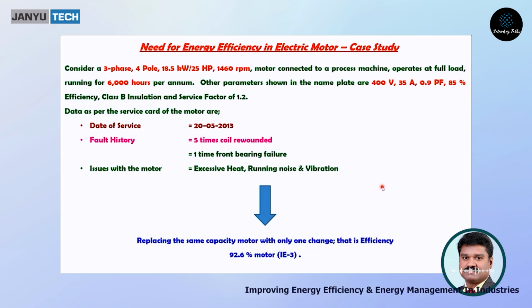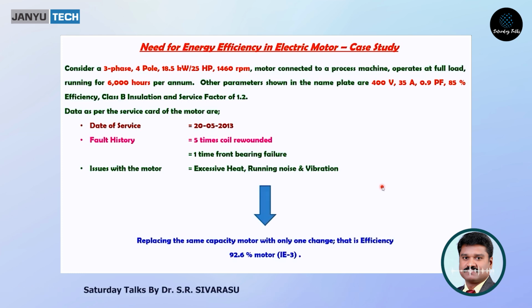Now you are asked to replace the old motor with a new motor, and you find out that the old motor does not have a nameplate. Or the nameplate is available, but the efficiency class is unknown, whether it is IE1 or the previous EFF1 or EFF2 class. But you decide to go for an IE3 motor. As you know, as per the Government of India, as per the BIS standard, any old motor can be replaced with at least an IE2 motor. IE3, IE4 depends on the management of the industry.